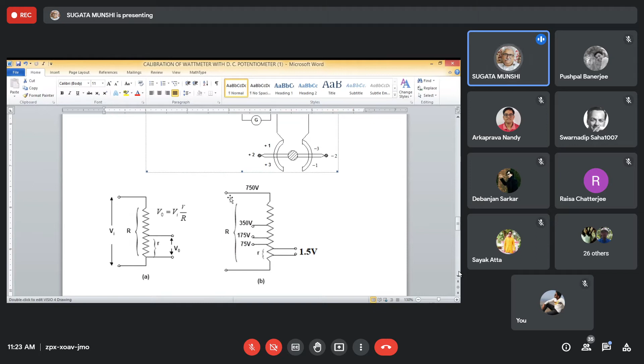So when you calibrate the wattmeter, you find out the error in measurement at those values. When it is indicating 10 watts, you have to find out whether the actual true wattage is 10 watts or not. When it is indicating 20 watts, whether the actual wattage is 20 watts or not, you have to find out. And if it is not, you have to find the error in every such case. That is the intention.